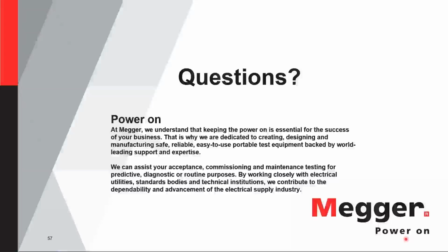So this test and these standards that we covered today in the webinar are only for dielectric breakdown. There's a different standard for power factor at 25 and 100 degrees, and if I'm not wrong, that's ASTM D924, and that one specifies a different test, and the instrument has to be totally different.